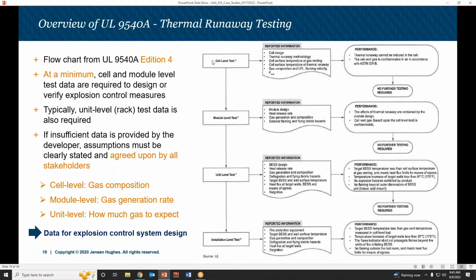This would be more important for the village hall people who would potentially permit a system like this. The full-scale fire test I was talking about is done on 4 levels: the cell level — pouches or cylinders — the module, the unit or IT rack, and then the whole installation. These tests measure different things like the LFL, gas composition, gas generation rate — how much gas we can expect. That's why this is important, and you can maybe just keep this as a cheat sheet.